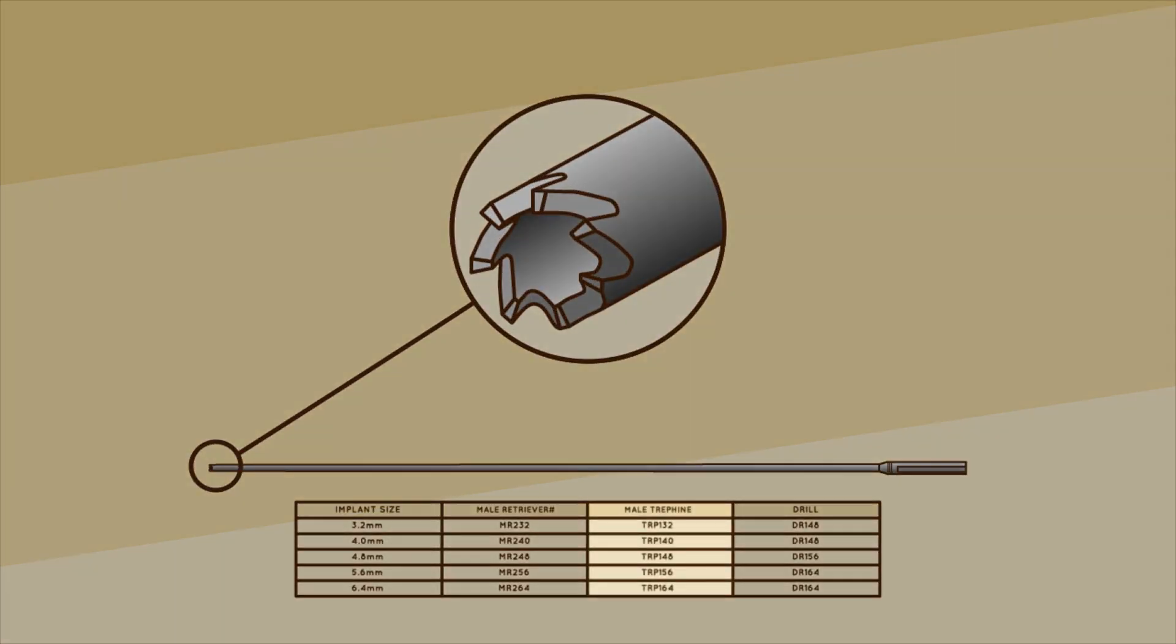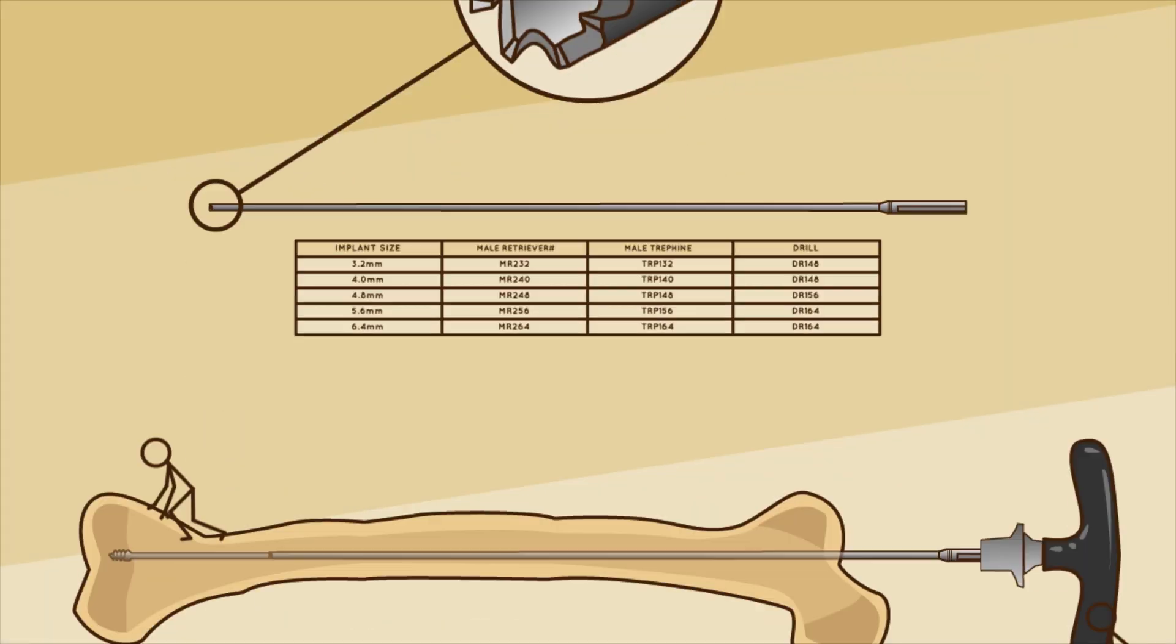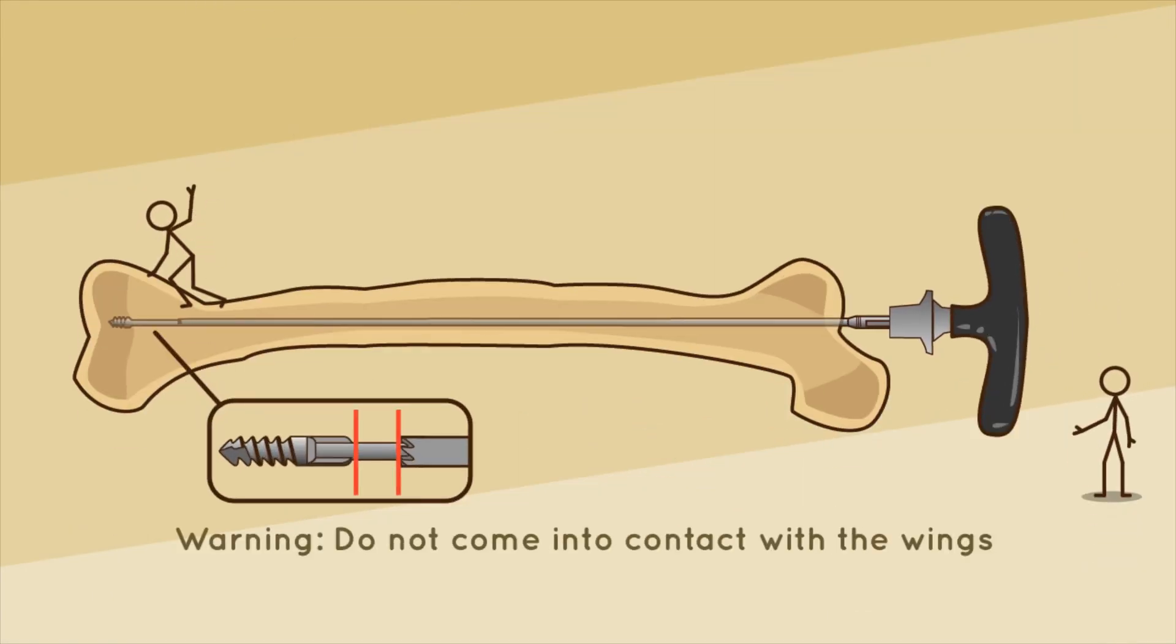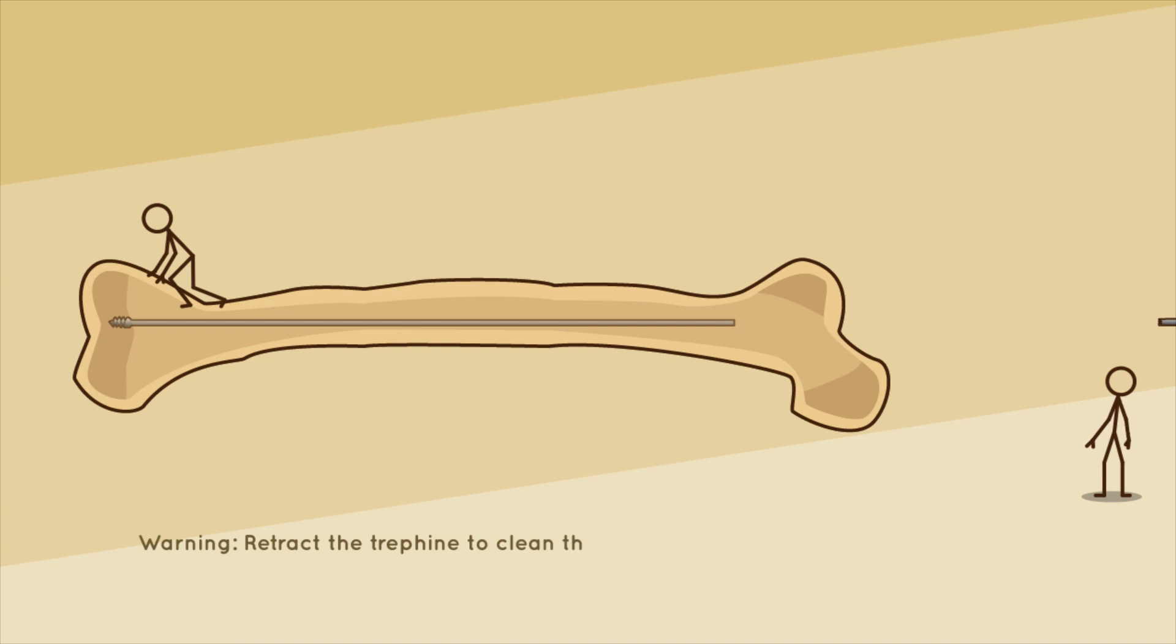A trephine of the diameter corresponding to the male components can be used manually or on power to clean a path for the male retriever. Take care not to come in contact with the wings of the male component when advancing the trephine. Warning: Retract the trephine to clean the teeth if advancement becomes difficult.